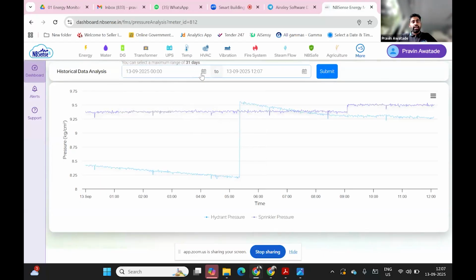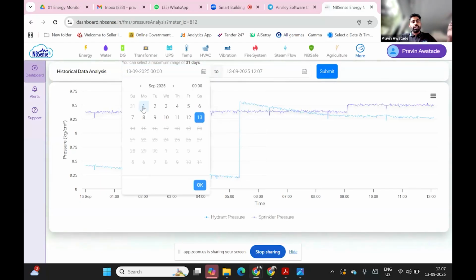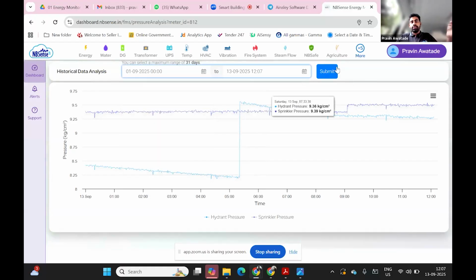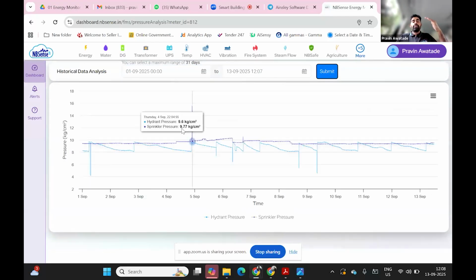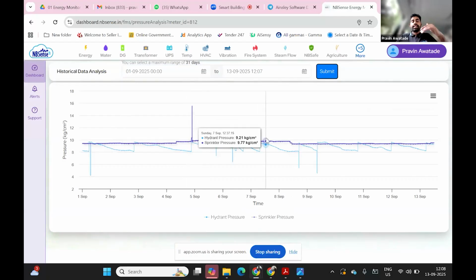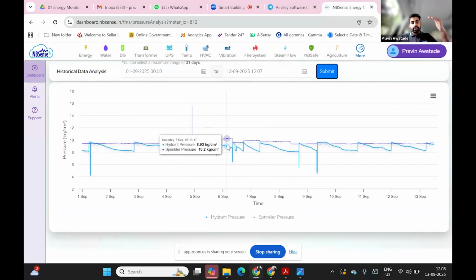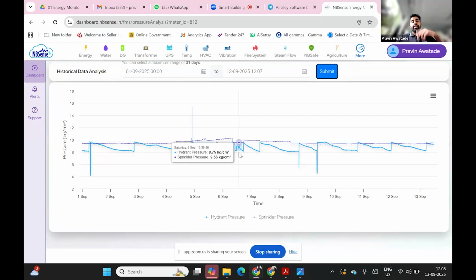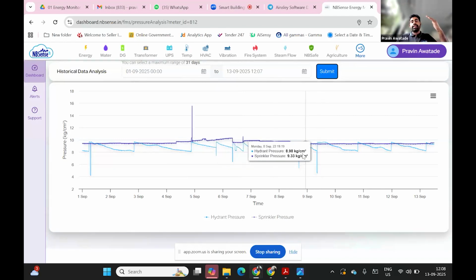Suppose the fire department wants to see, from the 1st of this month to the 13th, what was the pressure status, when it was high or low. This history is exactly what's needed post-incident, or during any incident, so it's very important. You can see there are ups and downs here. That's because at that time the jockey pump turned on and off many times, which created a surge. That surge line is there, that is the pressure recorded.